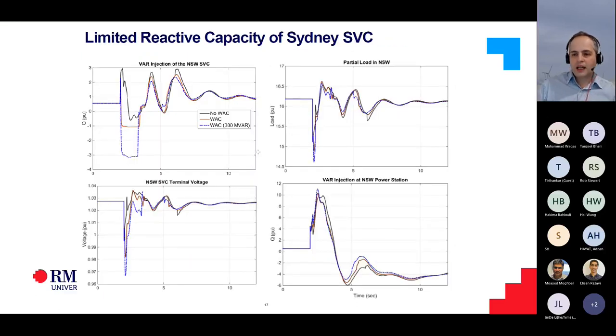One of the problems we faced in that specific scenario was that the reactive capacity of the Sydney SVC was a bit low. So we proposed that if we increase that reactive capacity to the same as the capacitive capacity - that SVC was plus 300 megavar, minus 100 megavar - if we make it plus minus 300 megavar, that would be further beneficial and would really increase the capability of that SVC in this type of controller. So by this type of control, we can also find places that could be potential good investments for improving system stability.